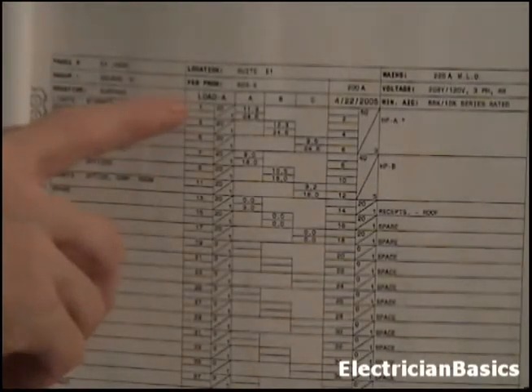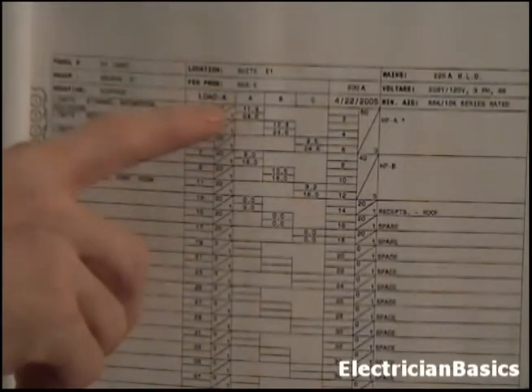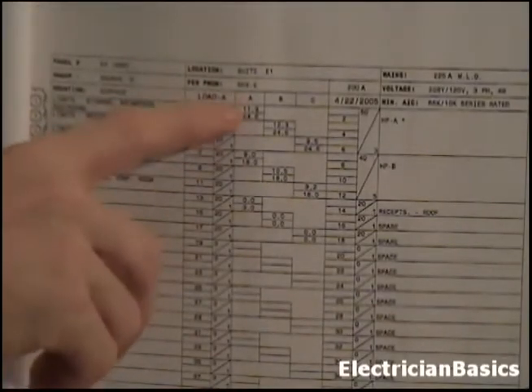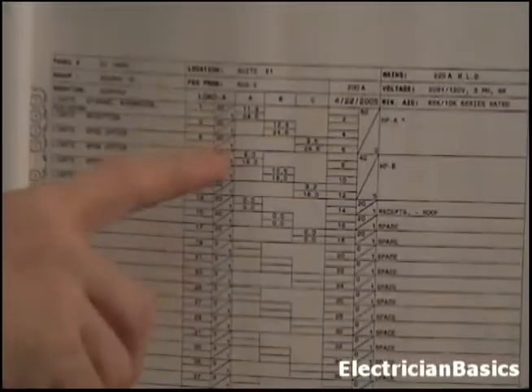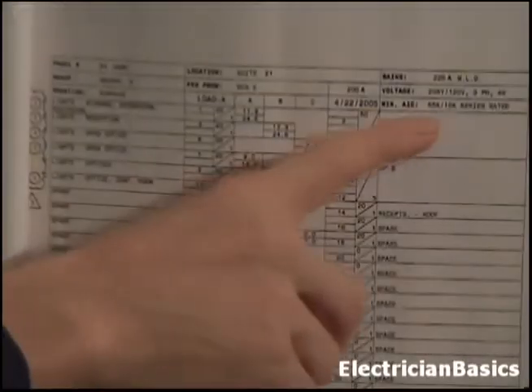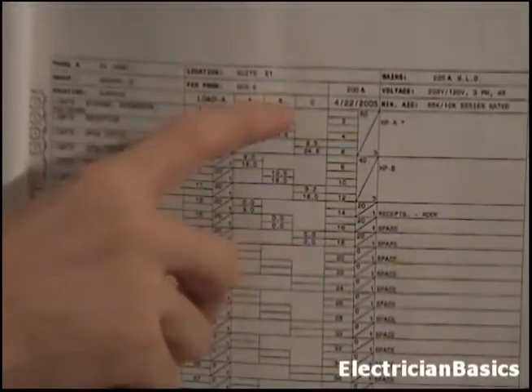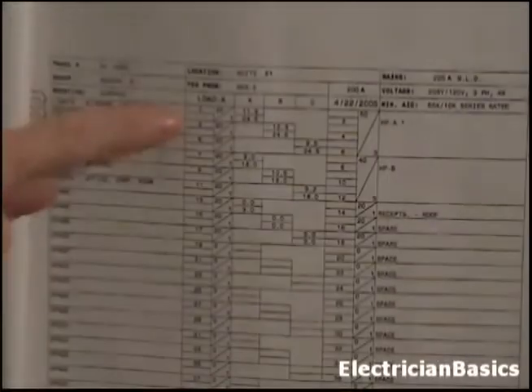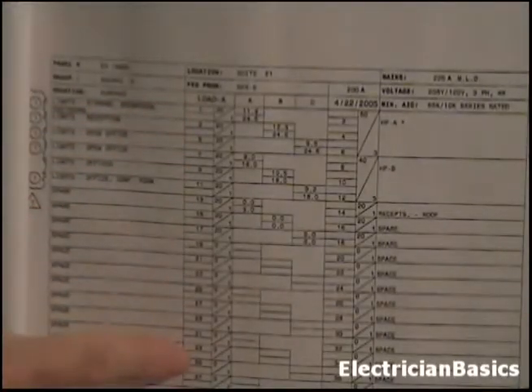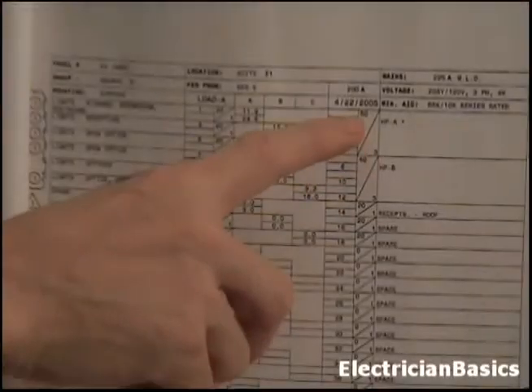Okay, now we read across here, has load, and A is the amps, reading down here. Okay, now it has A, B, and C. Now we saw that this was a three-phase, so this is A phase, B phase, and C phase. Now in your panel schedules, your odd numbers for your circuits are going to be on the left side. Your even numbers are going to be on the right side.